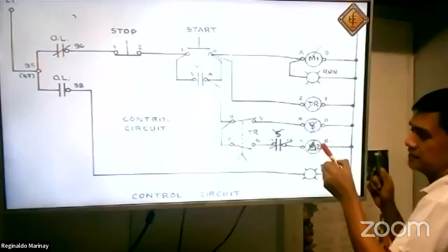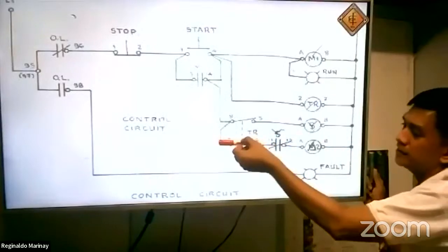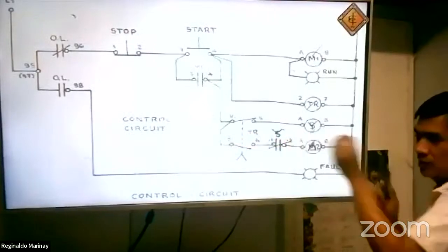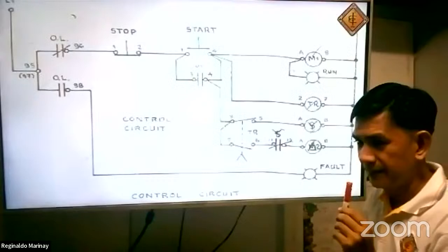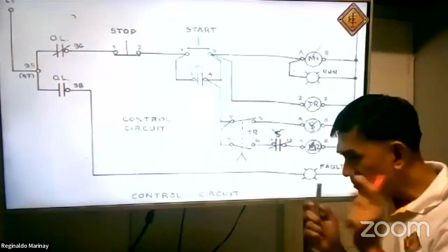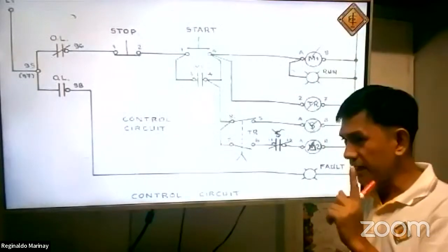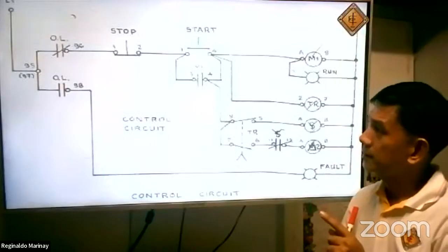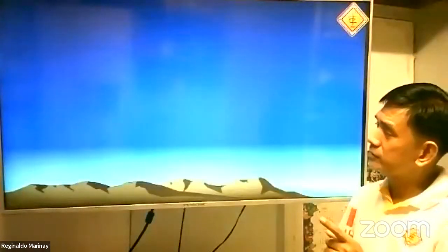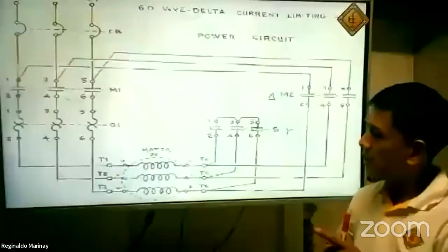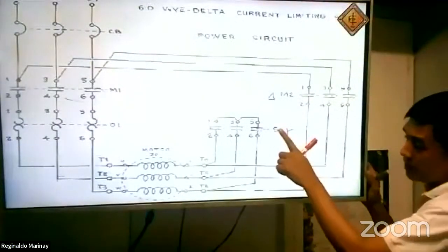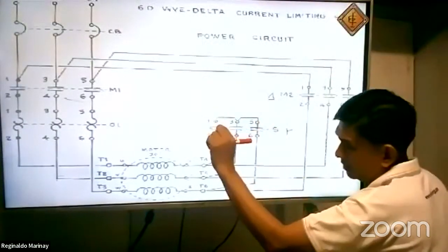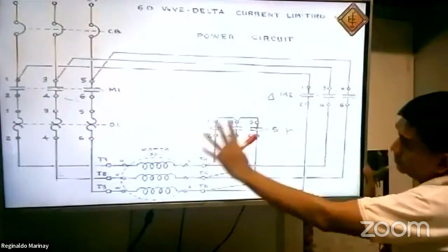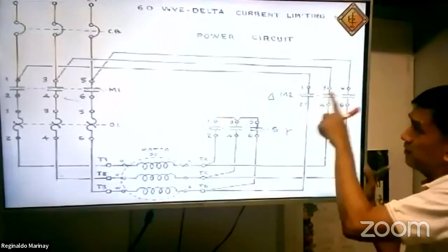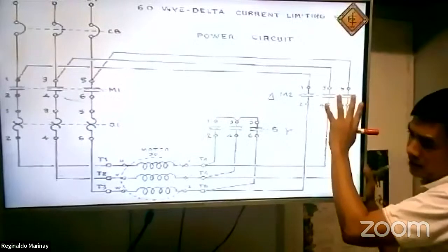Once you energize the delta contactor, what will happen? Remember, you already energized the delta contactor. Once you energize it, this thing would happen. Of course, the Y is de-energized. This will become open. We'll go back to its original position. This 3 will become closed, right? All at the same time.